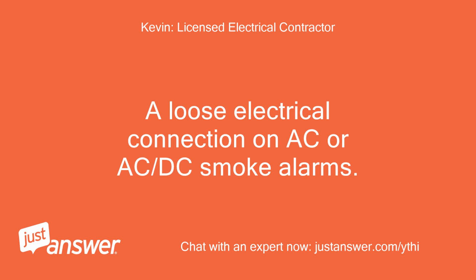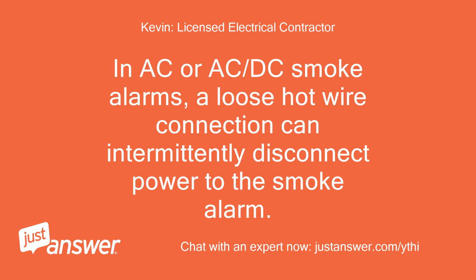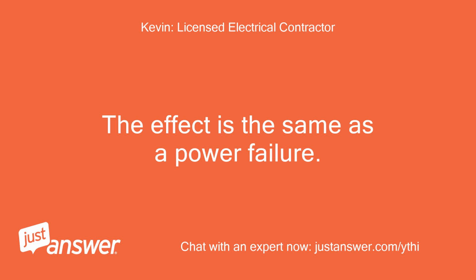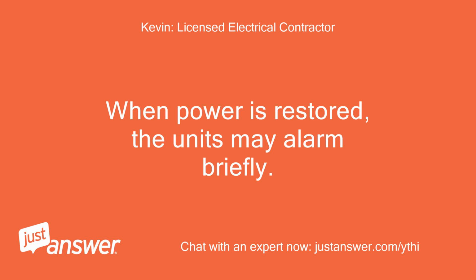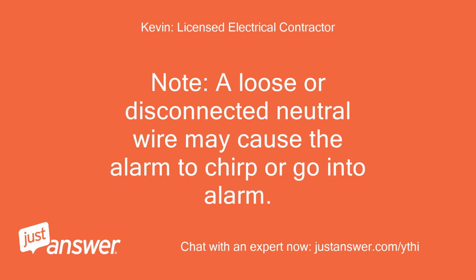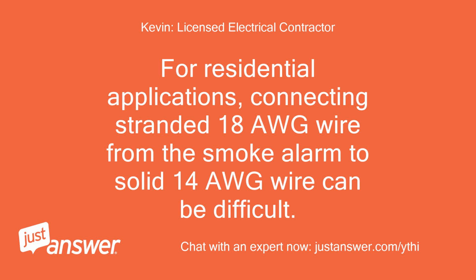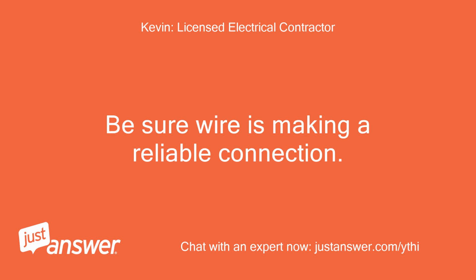A loose electrical connection on AC or AC-DC smoke alarms. In AC or AC-DC smoke alarms, a loose hot wire connection can intermittently disconnect power to the smoke alarm. The effect is the same as a power failure. When power is restored, the units may alarm briefly. Note, a loose or disconnected neutral wire may cause the alarm to chirp or go into alarm. For residential applications, connecting stranded 18 AWG wire from the smoke alarm to solid 14 AWG wire can be difficult. Be sure wire is making a reliable connection.